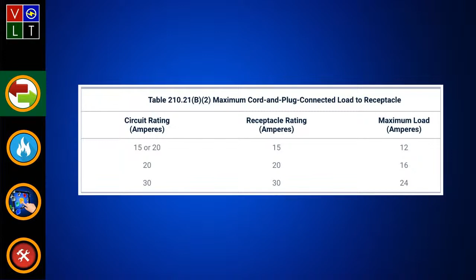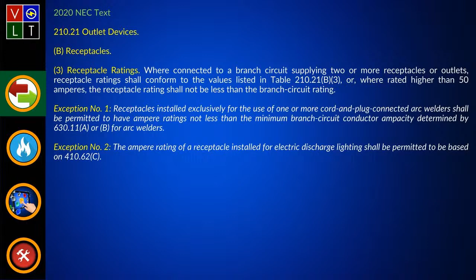These are the loads. And like David Englehart was saying, when you go to (B)(3), this is where you get into your receptacle ratings. You'll notice right here in the next table, this tells you what can be connected to that circuit. If you see 20 amp there, then come across and pick up your receptacle ratings. It says you can put a 15 or 20 amp receptacle on it, but a 15 can't be over 15. So there's your answer right there. That gives two different tables for people to look at to get the amperage rating for the receptacles, and then what type of receptacles can be installed based on the ampere rating of the circuit.